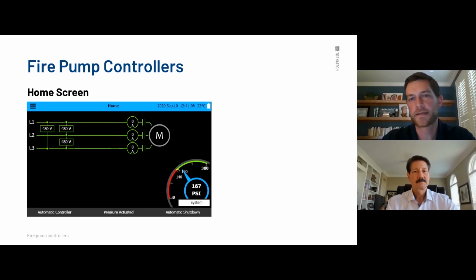And then you'll see that white mark. It's kind of hard to tell what that is, but that's actually our battery icon. The ViZiTouch has a battery that is being charged constantly, and that icon shows you the battery health on the top right there. The battery will last for the lifetime of the ViZiTouch, as long as power is running to it constantly. So looking at the screen, very simple, as Cole pointed everything out, you can walk up and look at the screen and get a picture of everything that's required by code in one single shot, with or without transfer. Green is on or go, red is off, yellow is caution or transition.